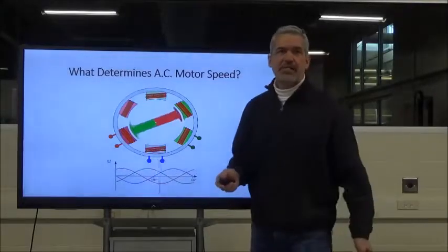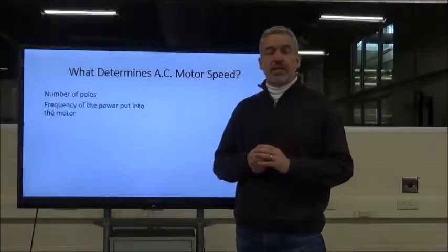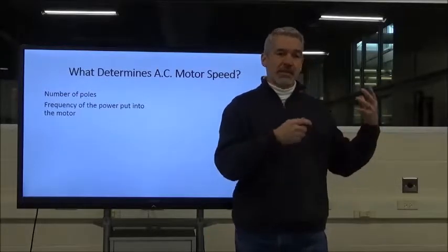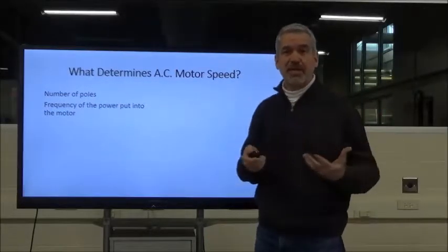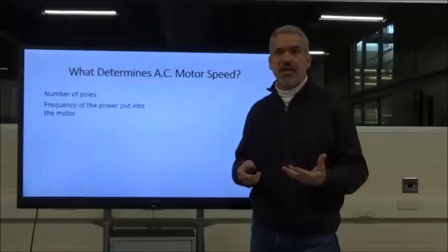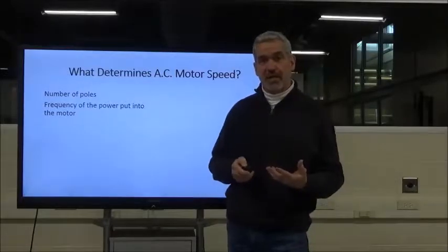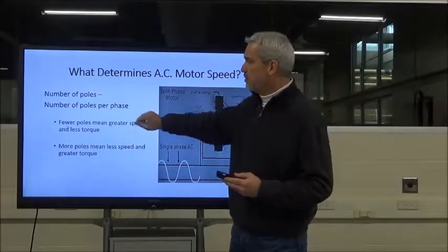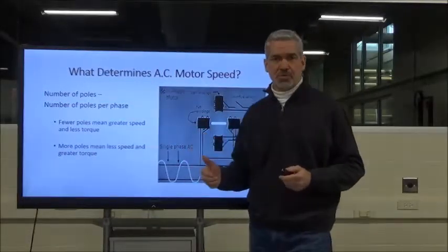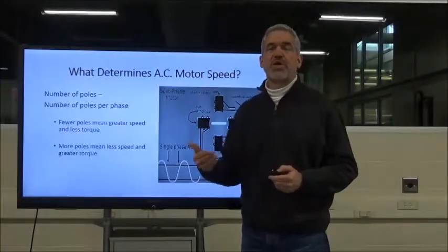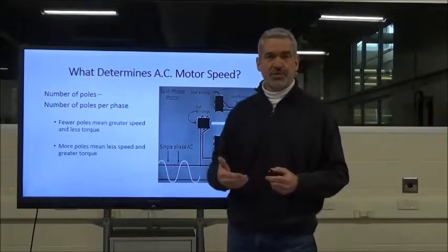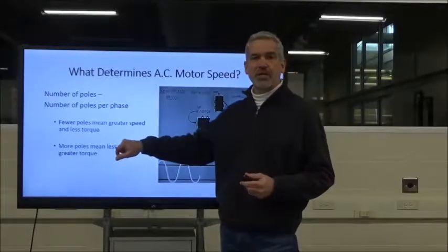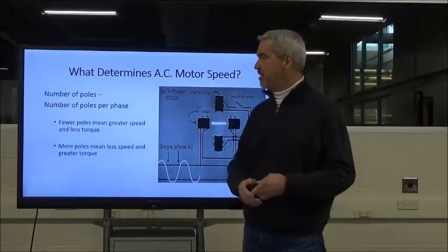What determines the speed of an AC motor? There are two factors: the number of poles in the motor, and the frequency of the power applied. In the United States, that frequency is 60 hertz. Regarding poles: fewer poles means faster RPM but less torque, while more poles means slower speed but greater torque.